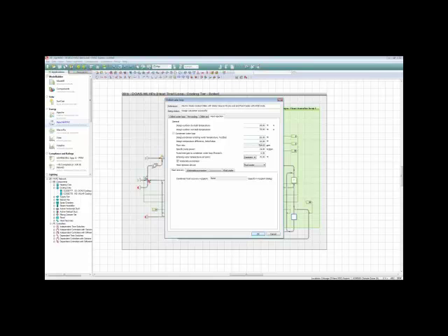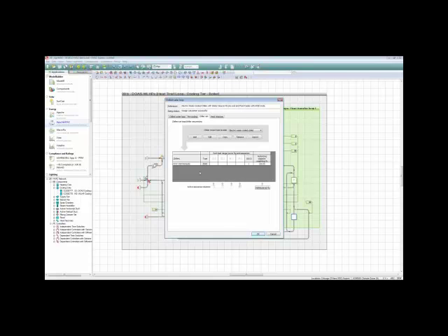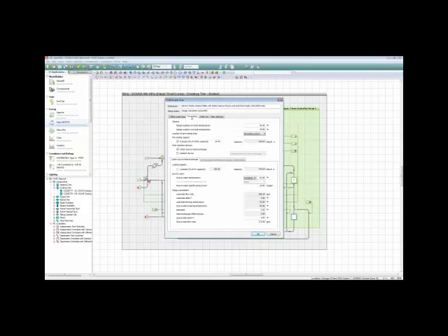The chiller set part of the dialog is the same as it's been in the past. In the pre-cooling part of it, which as I mentioned is ahead of the chiller set, this is normally on the secondary return, but you can also put it on the primary return, your choice. This has its own set of non-auto-sized outdoor conditions, and the assumption here is that whatever device you set up for pre-cooling might be intended to operate when, for example, in shoulder season, when the conditions are a bit more mild than the midsummer design condition for the chiller set.